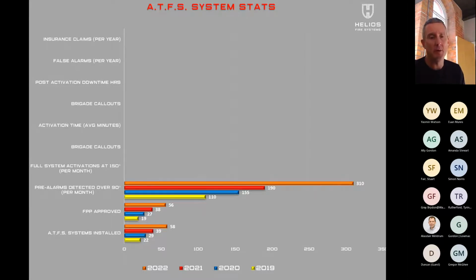Should we get thermal runaway, let's say we have a lithium-ion battery that's been compromised, which has triggered one of those 310 pre-alarms last month, and it achieves 150 degrees at 50 millimeters by 50 millimeters, you can see the activations we're actually getting here now.